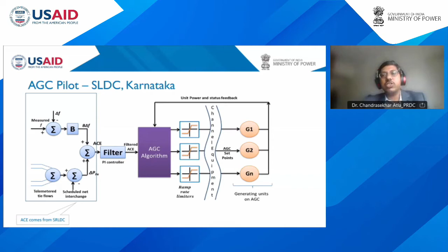And this module has been configured like a PI controller, AGC algorithm. This AGC module at the State Load Dispatch Center has been implemented with two-way communication, which means it is basically closed loop operation. So the response of the generators is continuously monitored in the time scale of 2 to 4 seconds, and then the required signal is given to the generators as per the area controller. In that case, you can maintain the deviation at the state boundary as near to your schedules. This is the philosophy adopted in the AGC implementation.